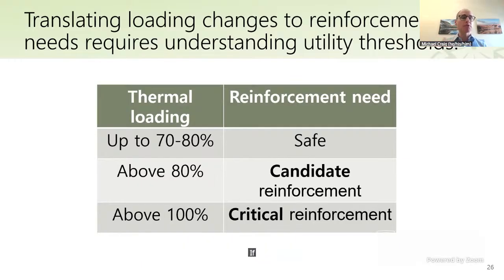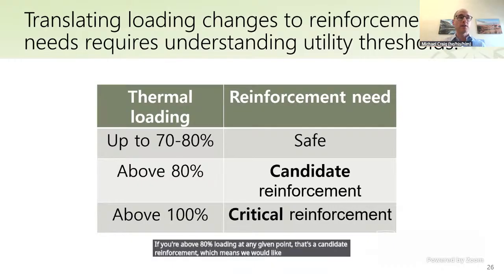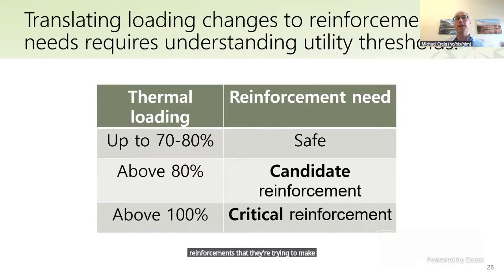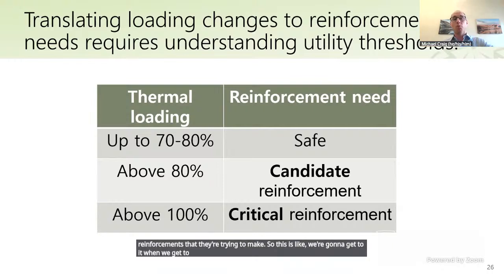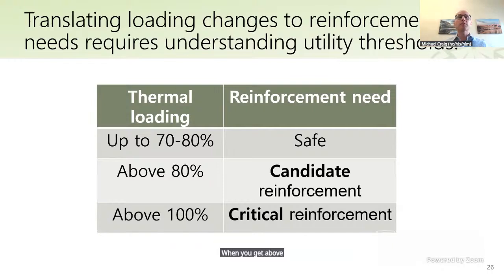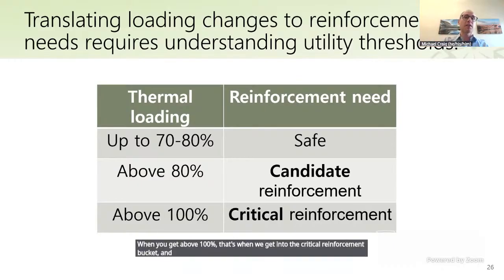If you're above 80% loading at any given point, that's a candidate reinforcement—we'd like to replace it, so it goes on our list of assets to replace and we get to it when we can. Most utilities across the United States have a backlog of reinforcements they're trying to make. When you get above 100%, that's the critical reinforcement bucket, which goes to the top of the line for replacement—urgent for a utility to deal with.